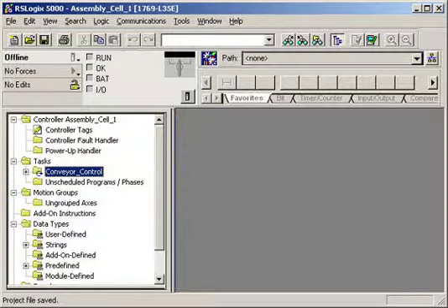In the unusual event that you want to prevent the external output modules from being updated to the controller's tag values at the end of the task scan, select the Disable Automatic Output Processing to Reduce Task Overhead checkbox and then click Apply. Read the warning and recommendation that are displayed. If you are sure that you want to prevent outputs from being sent automatically to the I/O module, click Yes.